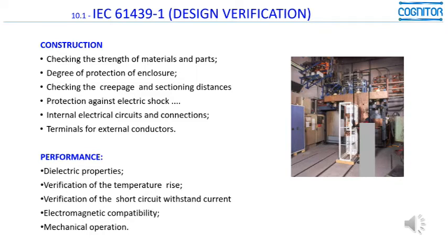For performance, the tests or verifications or calculations to be done are related to the dielectric properties, the verification of temperature rise, which is a very, very important item, and especially the users should be very careful with respect to the test reports issued by testing laboratories related to these aspects, because of something we explained in another part of this chapter, that the IEC 61439-1 does not state clearly what the temperature rise limits of connections, contacts, and so on are. And for this reason, the testing laboratories, most of the time, do not have a way to check if the equipment passed or not.